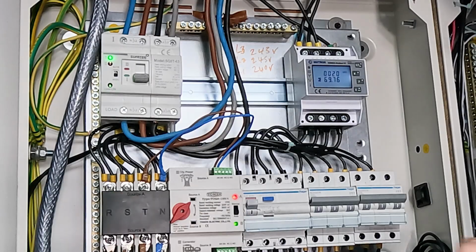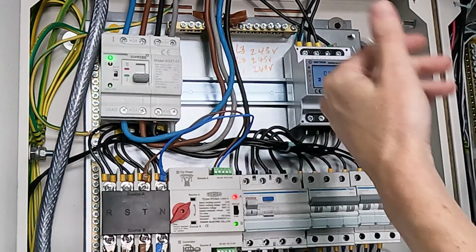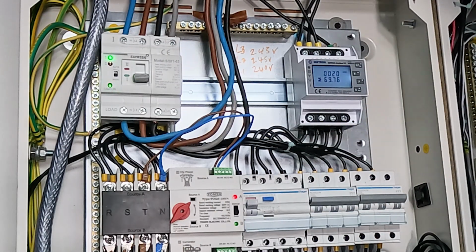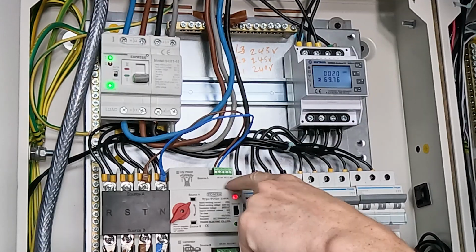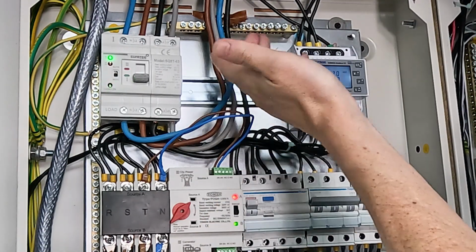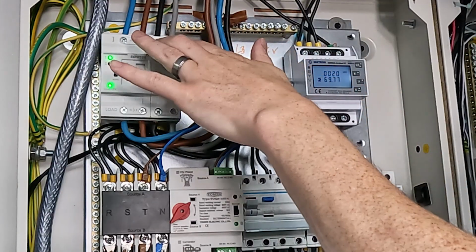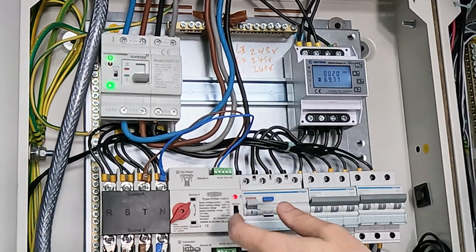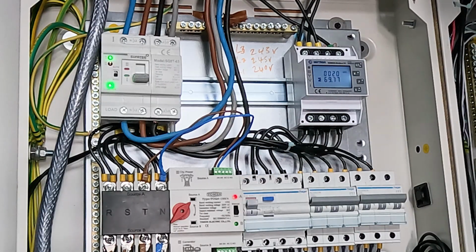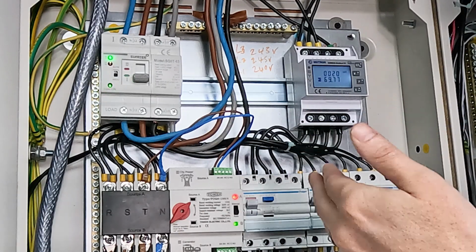Then I've got an ATS, a transfer switch. This is effectively a transfer switch as well, but this is the one I'm going to demonstrate today because it's slightly more complicated. You've actually got to do the connections for the automatic transfer to happen, whereas a switch like this does the detection already for you. This has got some extra customizations that you can do, but we're not going to worry about that. This is a very default state.